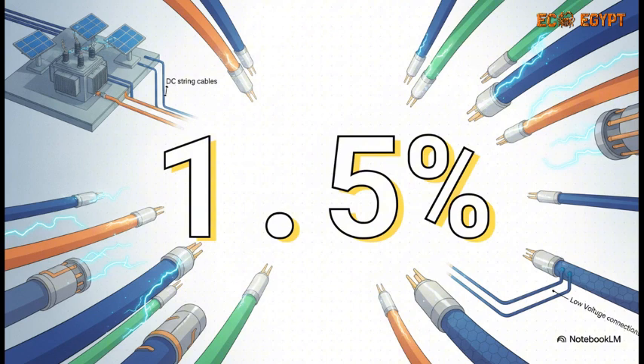We hit a seriously strict threshold here, 1.5%. Now, for your low voltage connections, you might occasionally see engineering allowances of up to 3 or 5%, depending on the plant. But for your primary power arteries, your DC string cables, and those massive MV feeders, hitting this 1.5% mark is critical. It literally stops catastrophic power bleeding over long physical distances before the energy can even reach the utility grid. It's a make or break number for the financial viability of the whole gig.